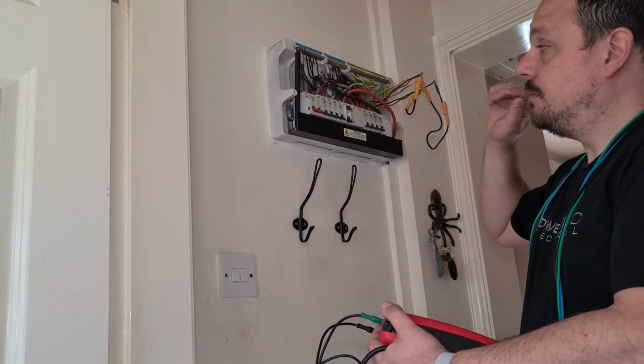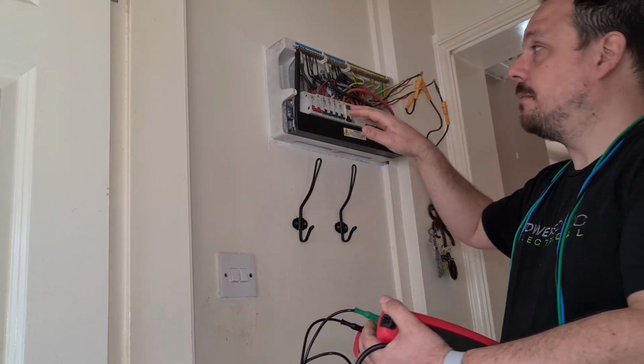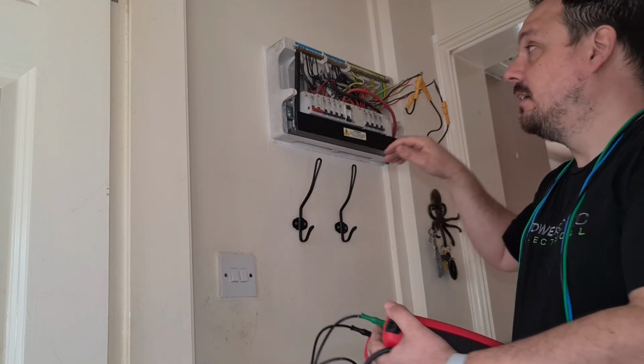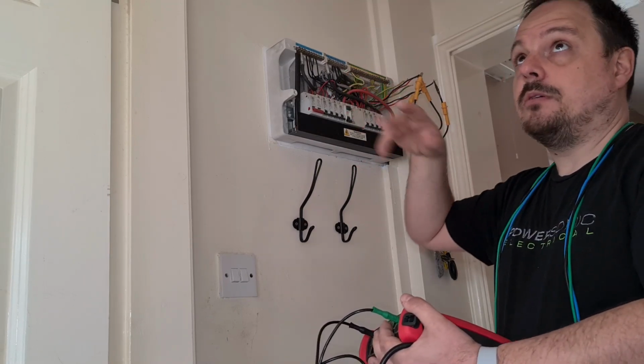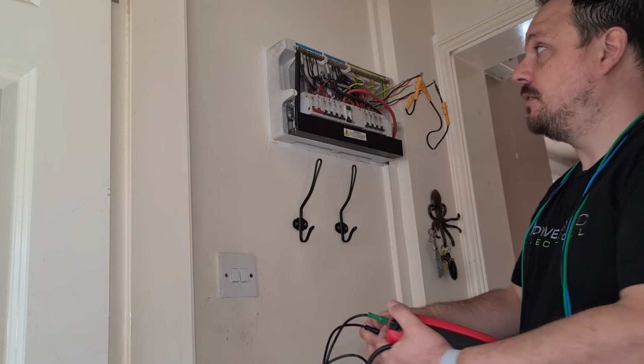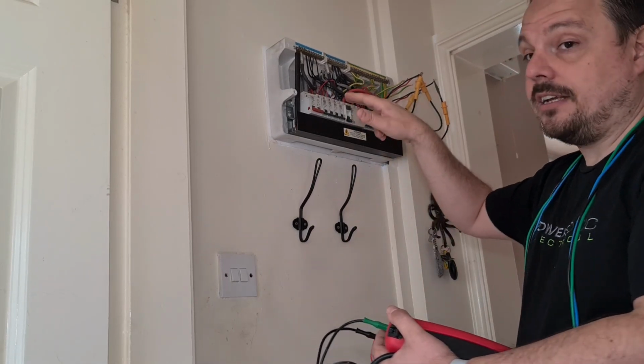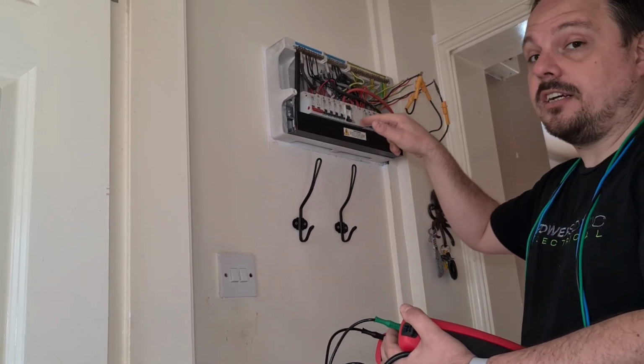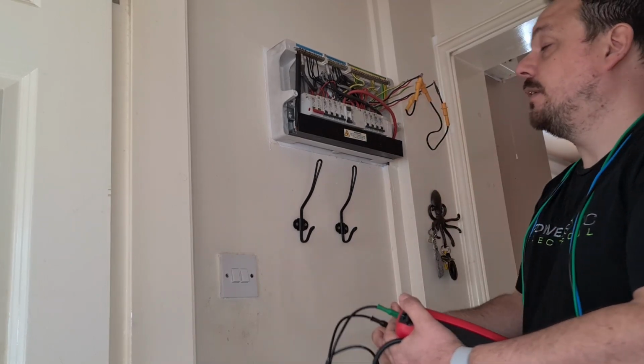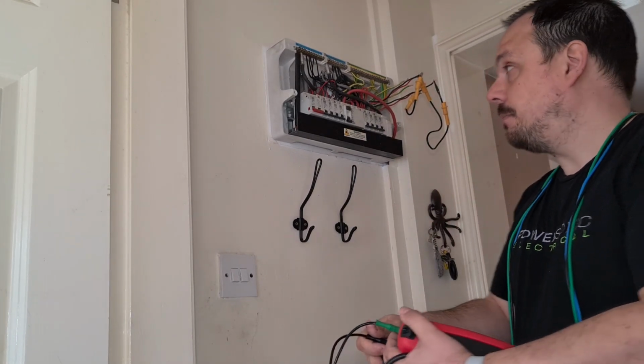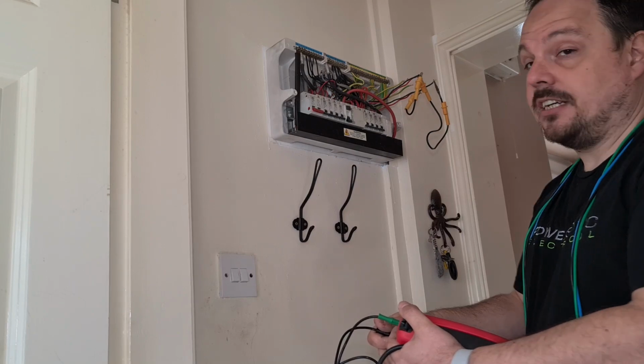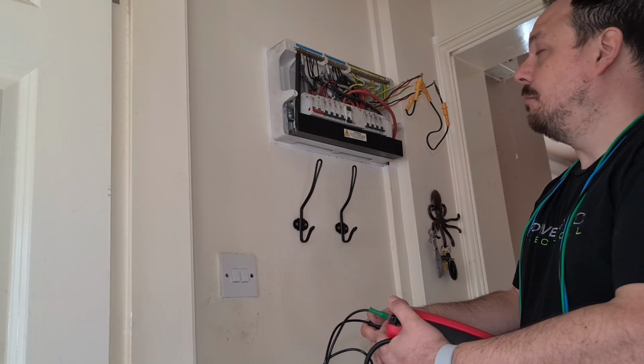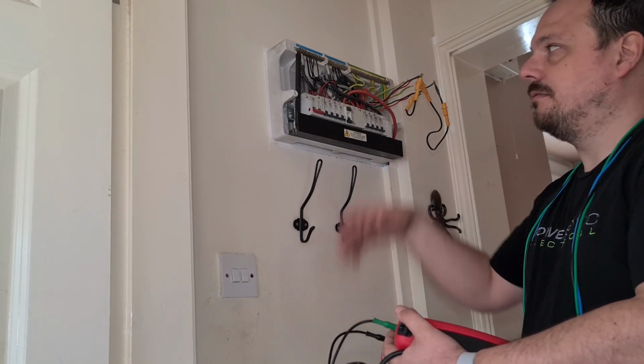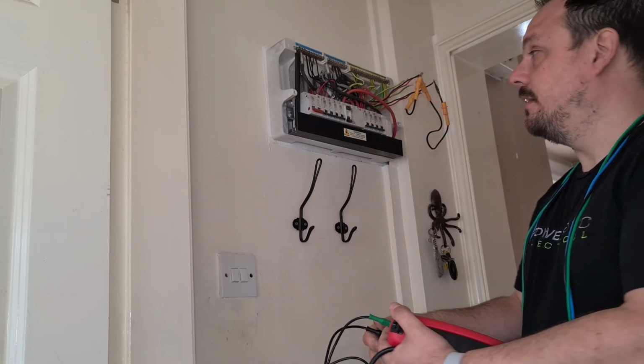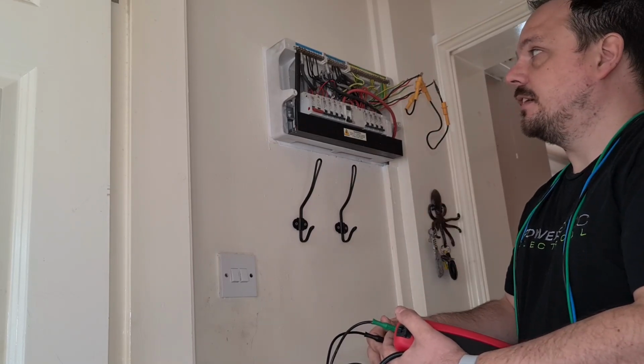And then you make a measurement between your, well, we'll show it, but I'm going to do this circuit by circuit. The reason is we've got lighting equipment connected, so I'm not going to be able to do a measurement, for example, between line and neutral on the lighting circuit, but I will be on the socket circuit. So we can just run through and quickly do that with everything connected up. So when we're at that stage, I'll cut back to the video and we'll do a quick IR test on the lights, for example, and then also on one of the socket circuits.